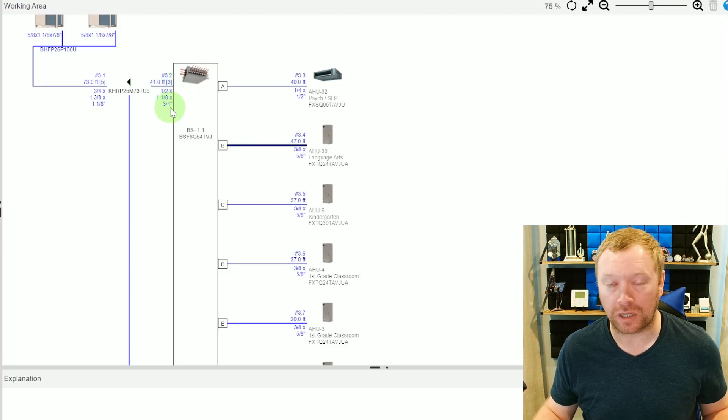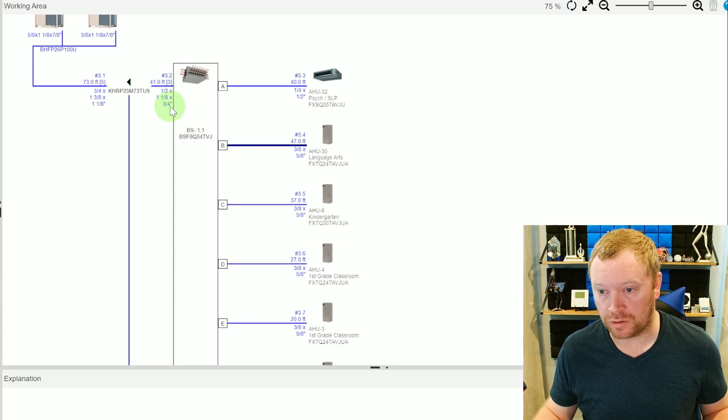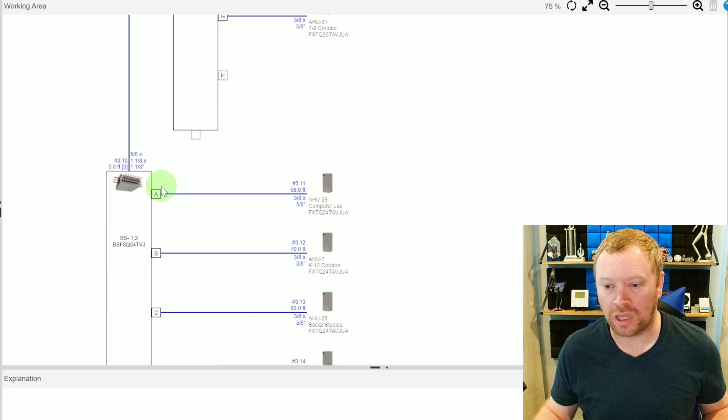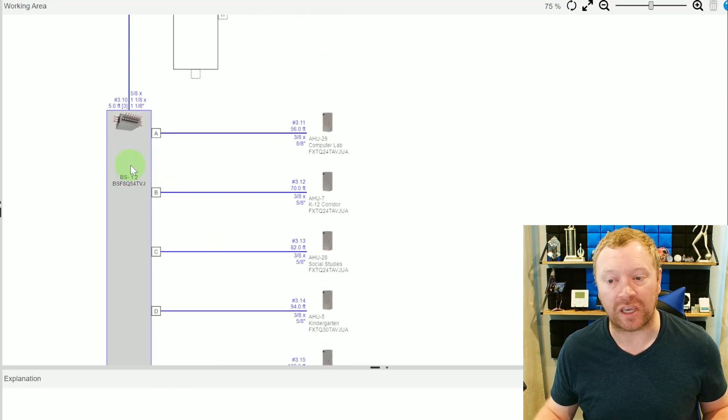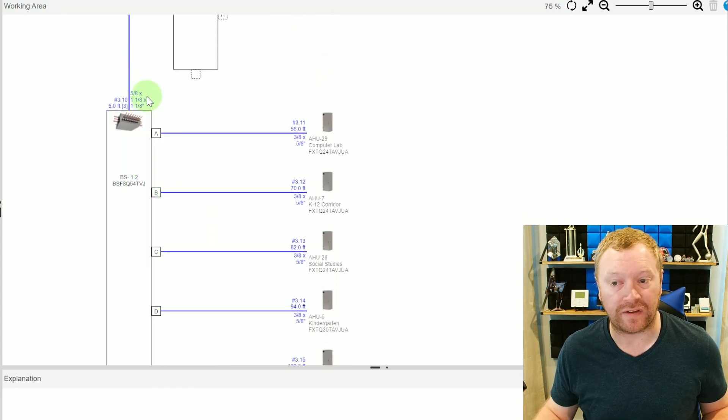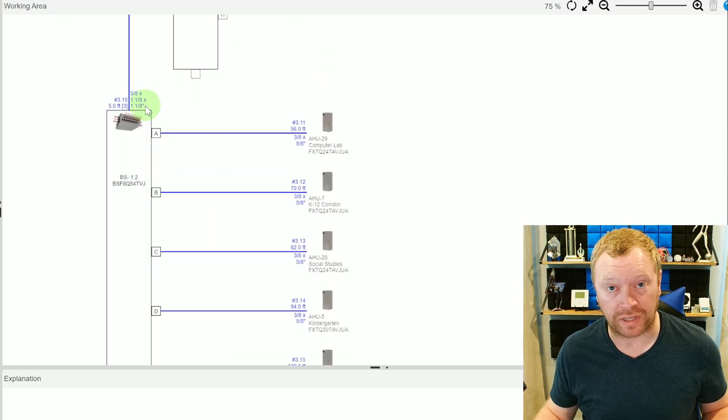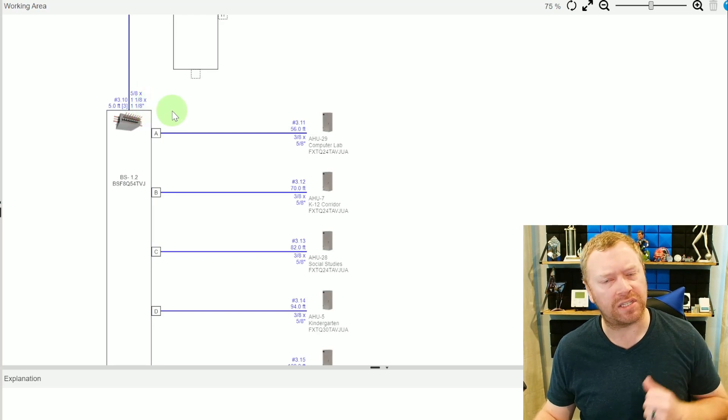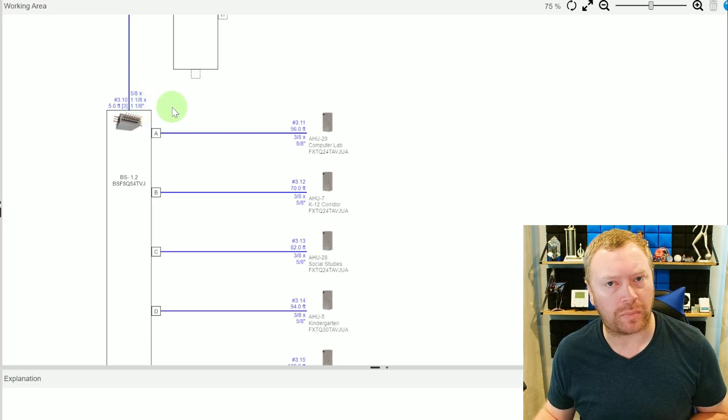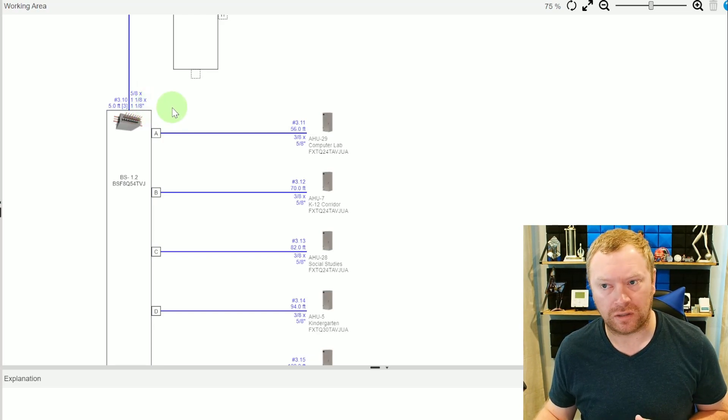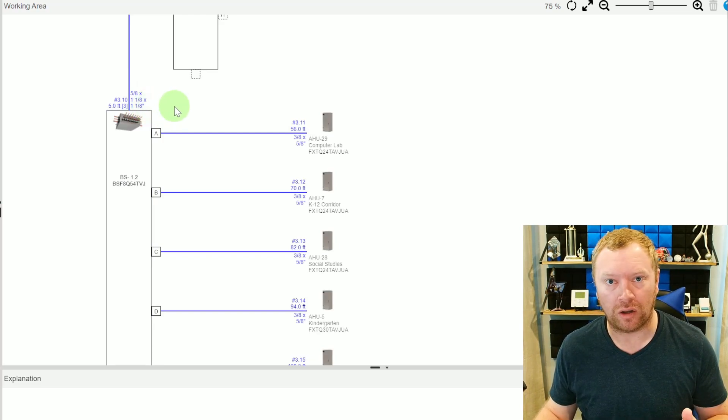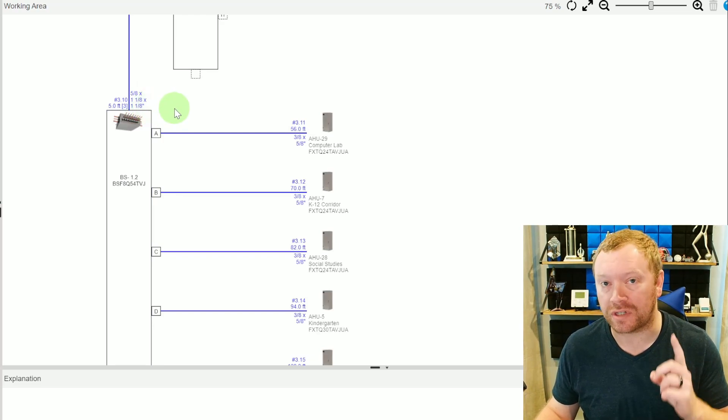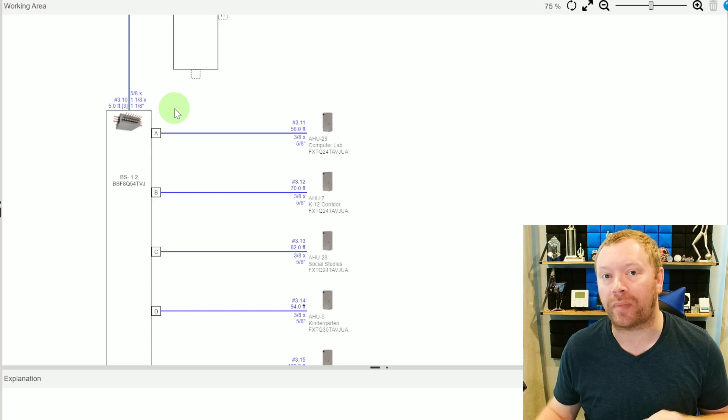In this particular case, we don't have a bunch of lengths that are super, super long. So it's not really that big of a deal, but here's what is a big deal. Notice that I have 41 feet going to BS 1.1 with all these indoor units connected. Now let's note that we have the five feet going down to BS 1.2 with all these indoor units connected. This is an eight port box. This is an eight port box. They are the same branch box. However, look at the pipe sizes. Half, one and one eighths, three quarters, going to this eight port box. But going to this eight port box, I have five eighths, one and one eighths, one and one eighths.